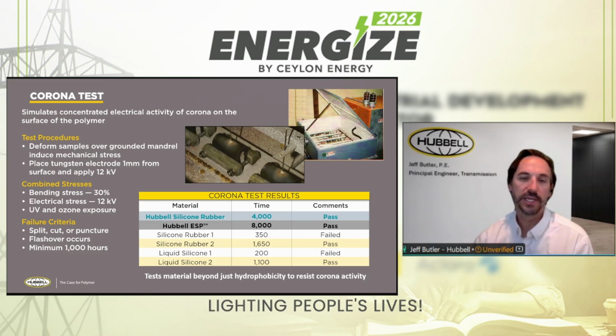Again, it was interesting to see the difference in the performance of what should have been similar materials. Between silicone rubber 1 and 2, liquid silicone 1 and 2, there were dramatically different results in the behavior of the polymers. Now you may be saying, well, maybe there was a bad sample or it was mixed improperly, but this test was done with multiple plaques. 5 samples were taken, and it was averaged across multiple samples of the rubber to determine these results. And as the note at the bottom says, this test goes beyond just the hydrophobicity. Many times hydrophobicity becomes the key characteristic for silicone rubber and becomes the focus. But this demonstrates that hydrophobicity is only one aspect of silicone rubber that is important; the durability and performance of the rubber itself is still very important beyond just the hydrophobicity.